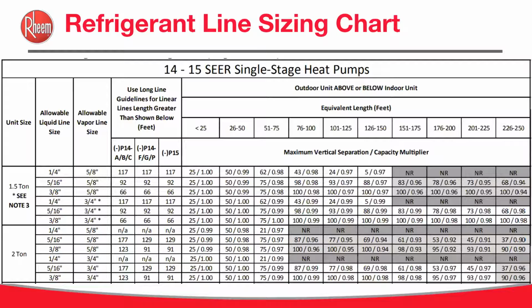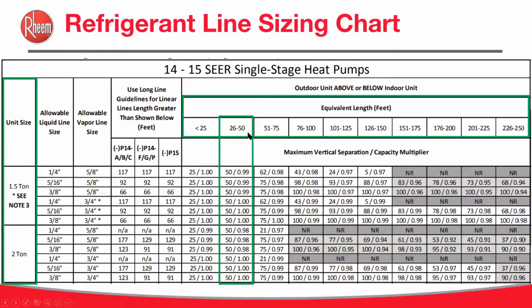Okay, now that we know what the lines do, let's go through the steps to select the proper liquid line and suction line. So first of all, we got to pick the unit size. So here, what we're going to do is we're going to look at it and we're going to pick a 1.5 ton unit. We're then going to have to know what the equivalent length is. So in this case, what we've done, we've picked a 45-foot line set. So with a 45-foot line set, we're going to be in this area because the line set equivalent length is 26 to 50 feet.